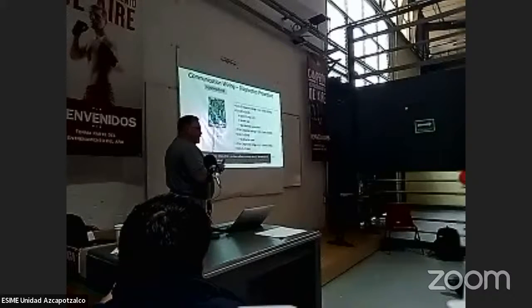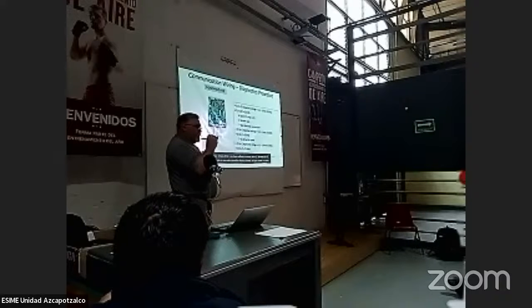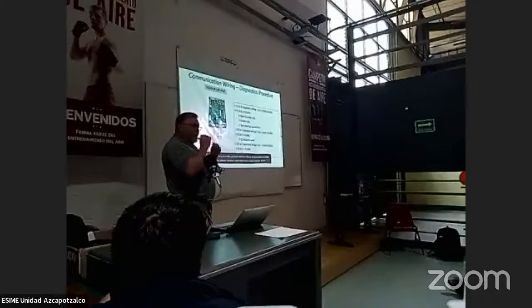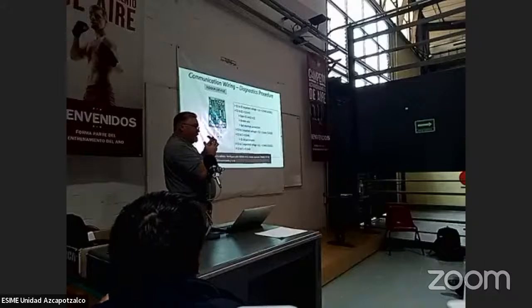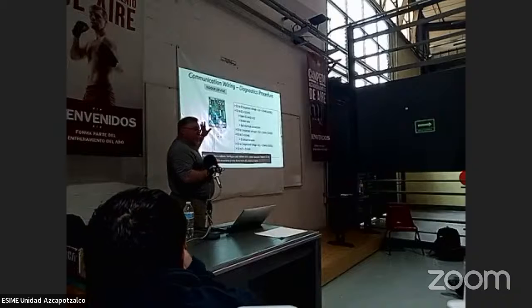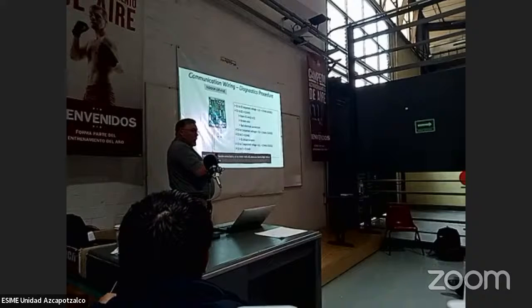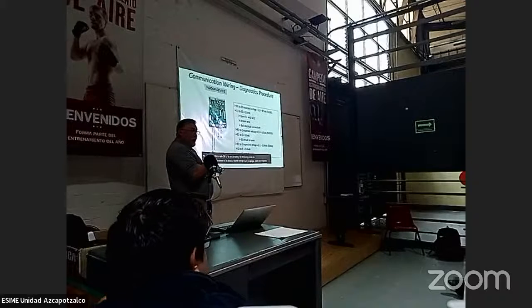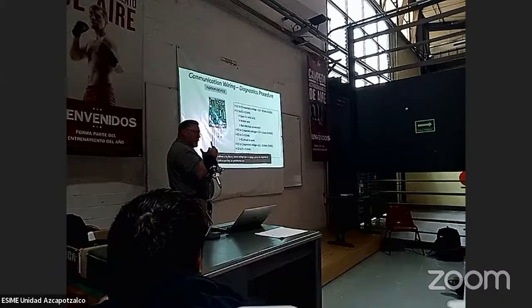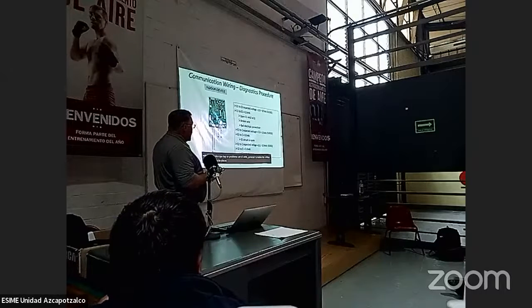Same thing. So like I was telling you, check the board. Check each board the same way. Remove the E1, E2, be power connected. And if you don't have anything there, then you've got something else going on. If the board checks out okay, and you power it up, and you put the E1, E2 wires back on the board, and you've got voltage going out, but no voltage returning, then that tells you there's a problem with the wire, correct? If all voltages check, if all boards check out okay, right? So don't be so quick to get the board.